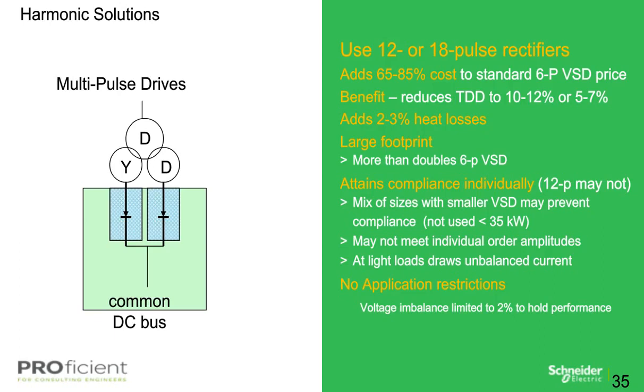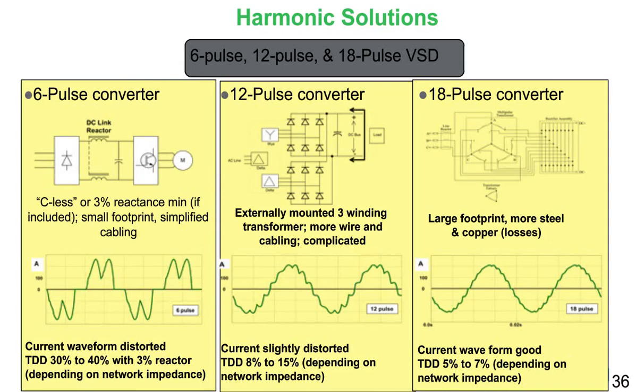So if we take a step back and take a look at the waveforms of a standard 6-pulse converter, 12-pulse converter, and an 18-pulse, what we show is the waveforms. Focusing our attention on the 6-pulse, you see the current waveform distorted at TDD 30% to 40% with the 3% line reactor. And again, all of them depend on network impedance. But as you can see, that's a very choppy waveform, and you're getting quite a few harmonics on the line there.